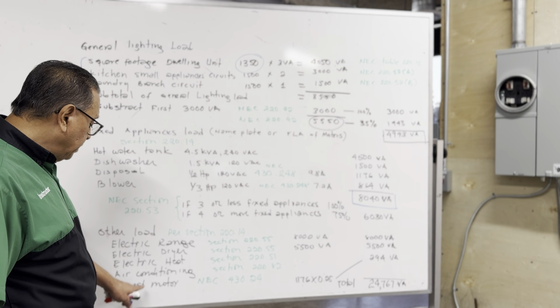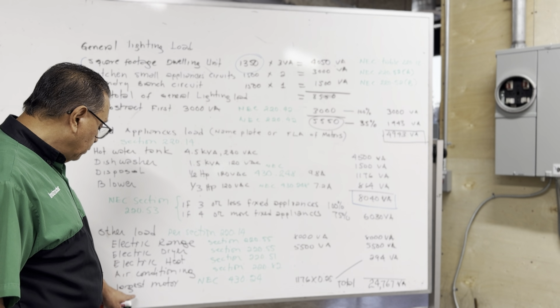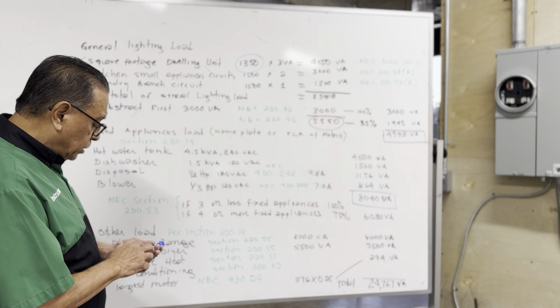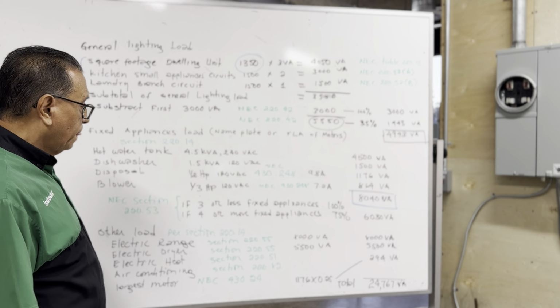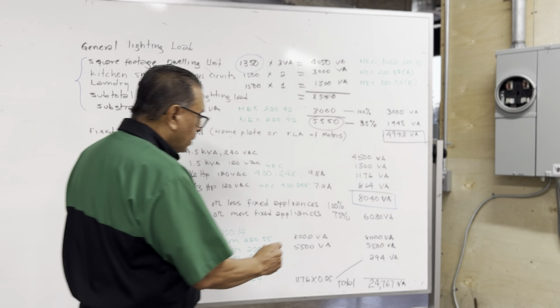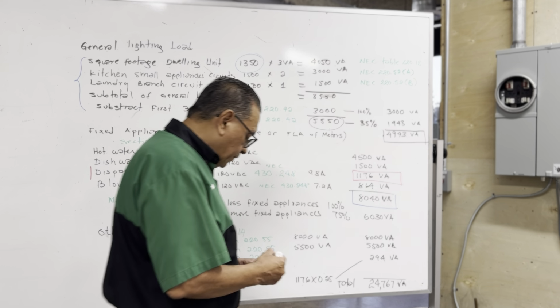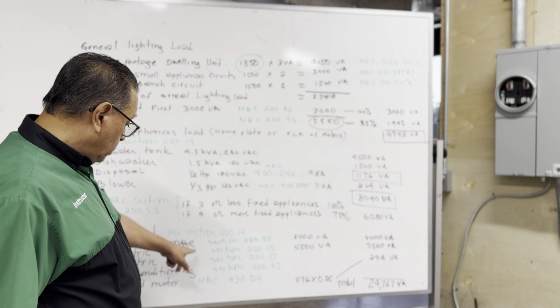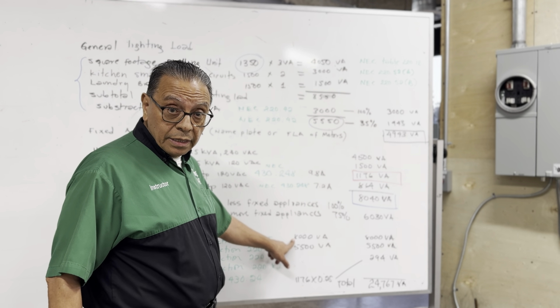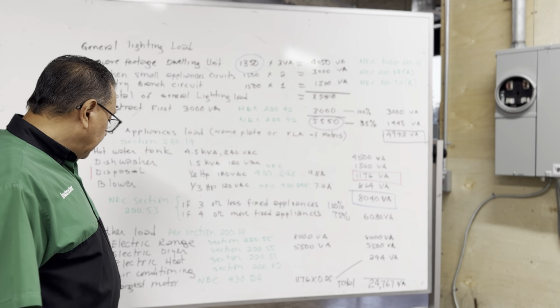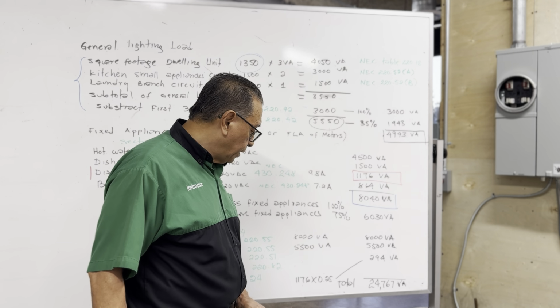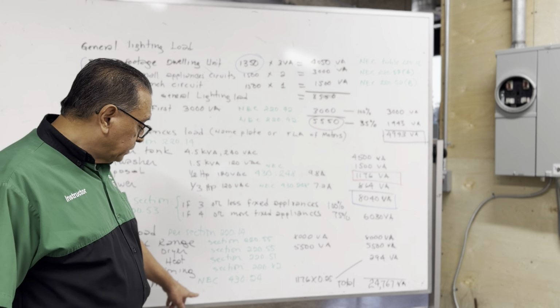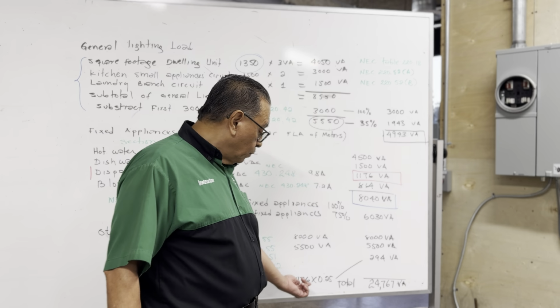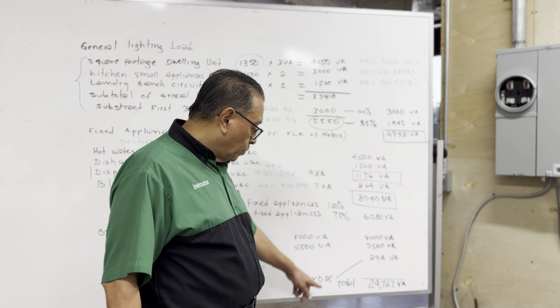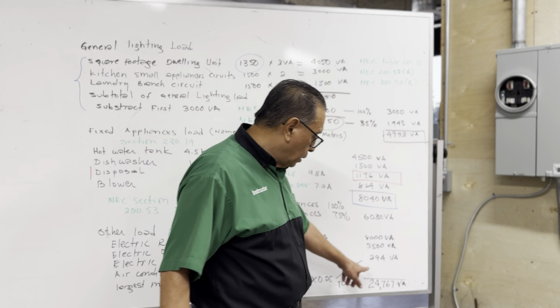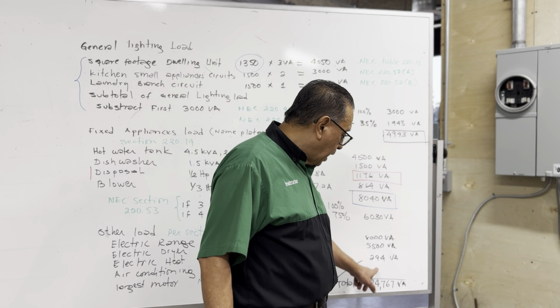And on the other loads, per Article 220.14, I have the electrical range, the electrical dryer, the electrical heat, the air conditioning, and I should include the largest motor, which is this one. This is my largest electrical motor. I use the nameplate information: the electrical range, 8,000 volt ampere in this hypothetical scenario, and the electrical dryer, 5,500 volt ampere. And the largest motor, per Article 430.24, I need to multiply the volt ampere times 0.25, in other words, the 25%, for a total of 294 volt ampere.